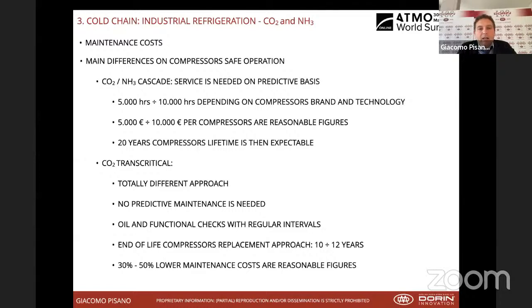Typically, compressors need a full overhaul between 5,000 and 10,000 hours of operation. Reasonably, you can think about 5,000 euro to 10,000 euro per compressor per maintenance. And in this case, a 20 year compressor lifetime is definitely expectable.